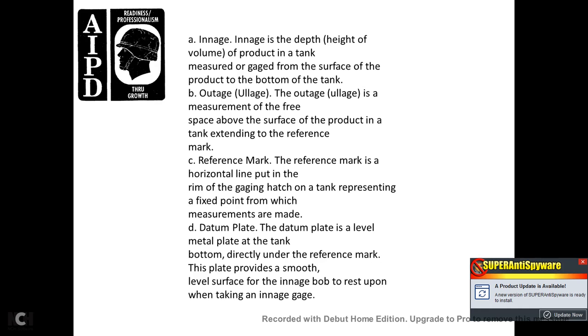The reference mark is a horizontal line put on the rim of the gauging hatch on the top of the tank, representing the fixed point from which measurements are made. The datum plate is a level metal plate at the tank bottom directly under the reference mark. The datum plate provides a smooth level surface for the bottom bob to rest upon when taking an ingage measurement.